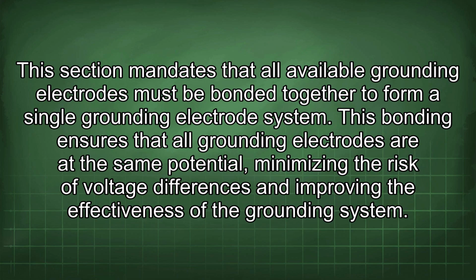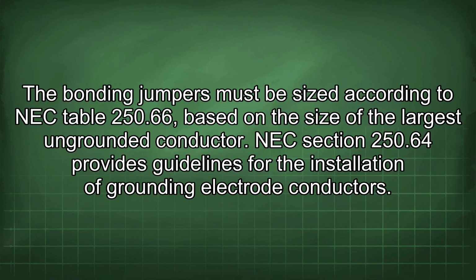This section mandates that all available grounding electrodes must be bonded together to form a single grounding electrode system. This bonding ensures that all grounding electrodes are at the same potential, minimizing the risk of voltage differences and improving the effectiveness of the grounding system. The bonding jumpers must be sized according to NEC Table 250.66, based on the size of the largest ungrounded conductor.